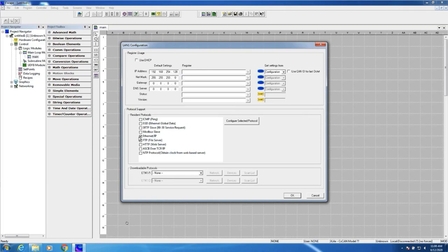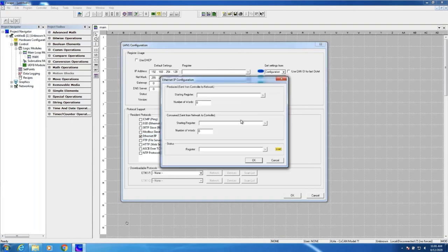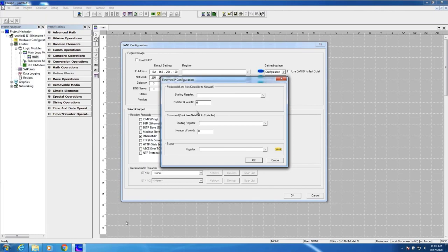To enable Ethernet IP, all I have to do is make sure the Ethernet IP checkbox has been checked. While it's highlighted, I press 'Configure Selected Protocol.' Now it's a matter of assigning the starting variable or variable array for the data I'm going to be producing. Keep in mind that's my input assembly, because the assembly is always referenced from the point of view of the scanner. So my input assembly is what I'll be producing, and my output assembly is what I'll be consuming from the scanner. I'll be assigning array-type variables as well as the number of consecutive words in that array, making up the total size of my input and output assemblies.